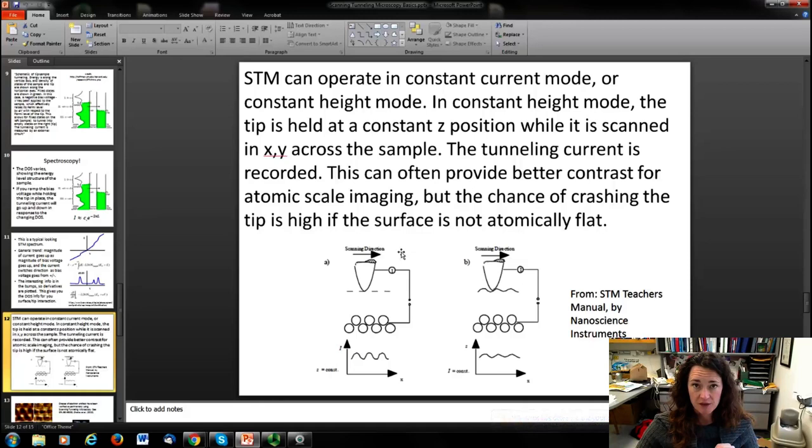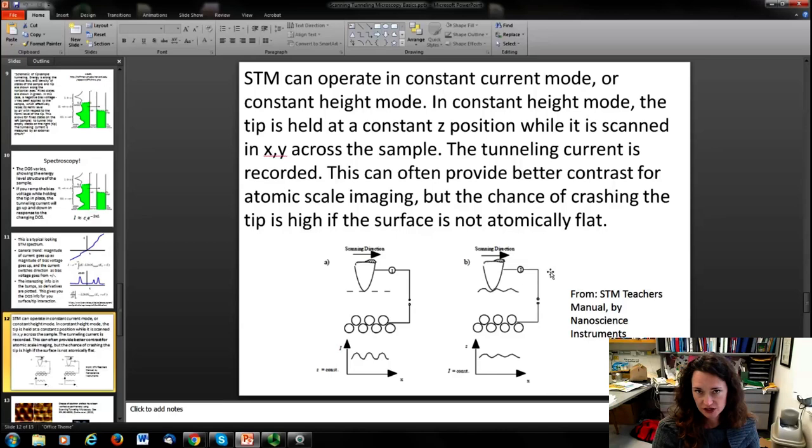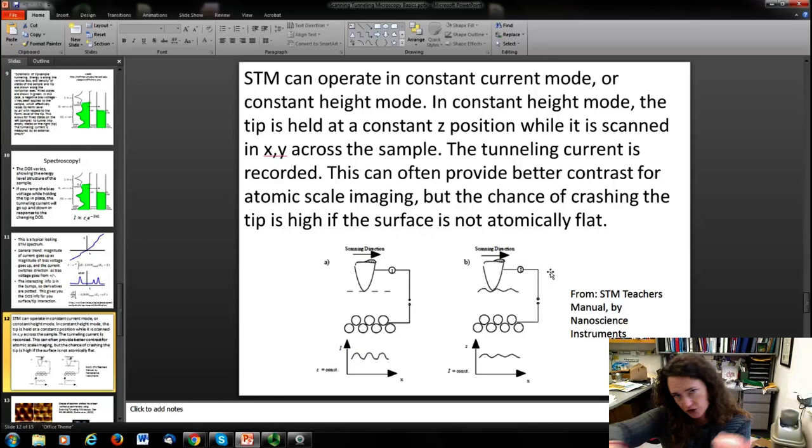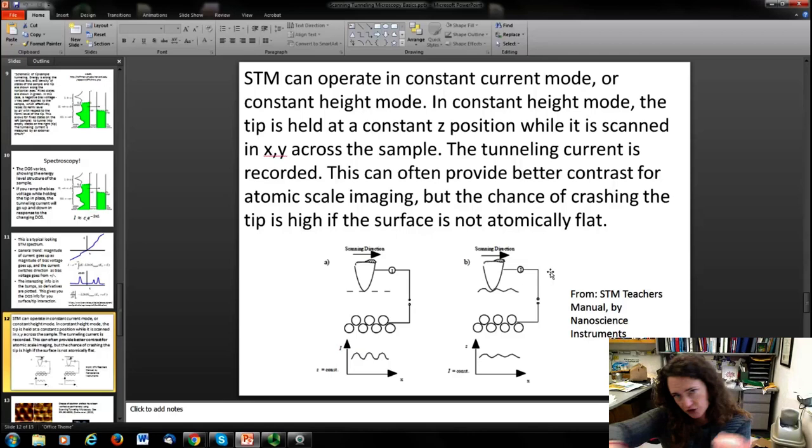But you've got to be careful. You've got to first scan the surface in constant current mode and make sure you really are on an atomically flat region and that your sample's not tilted. Because you might crash your tip — your tip sees a bump on the surface and instead of retracting in time to get over it, it just plows right through. That's a tip crash, which is bad for STM imaging, and unfortunately, it's really super common.